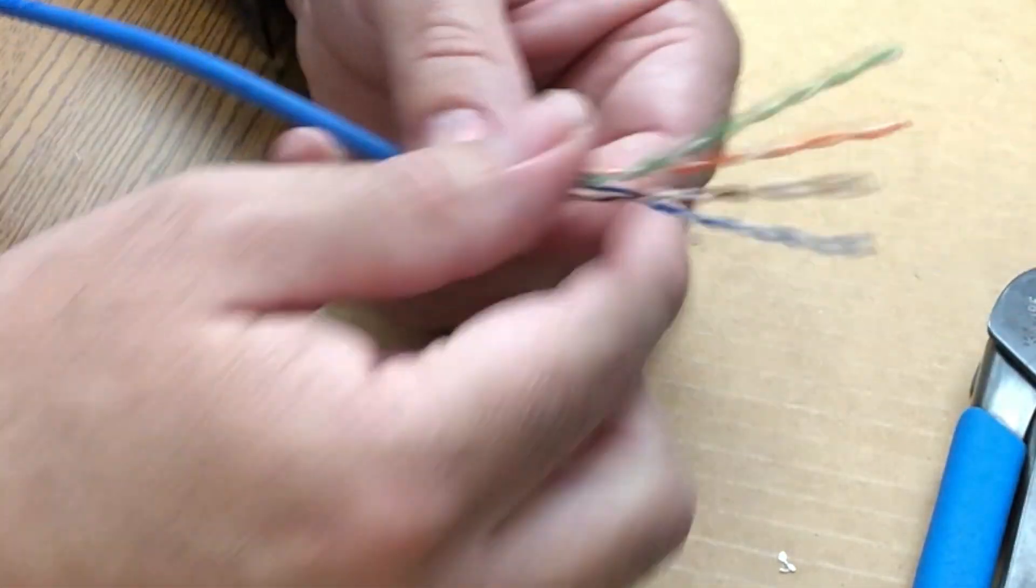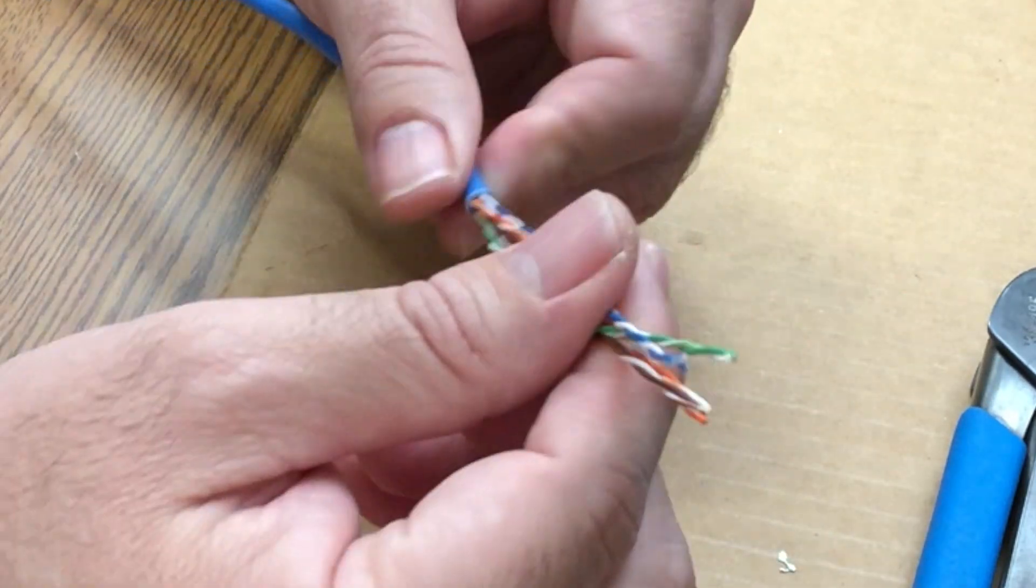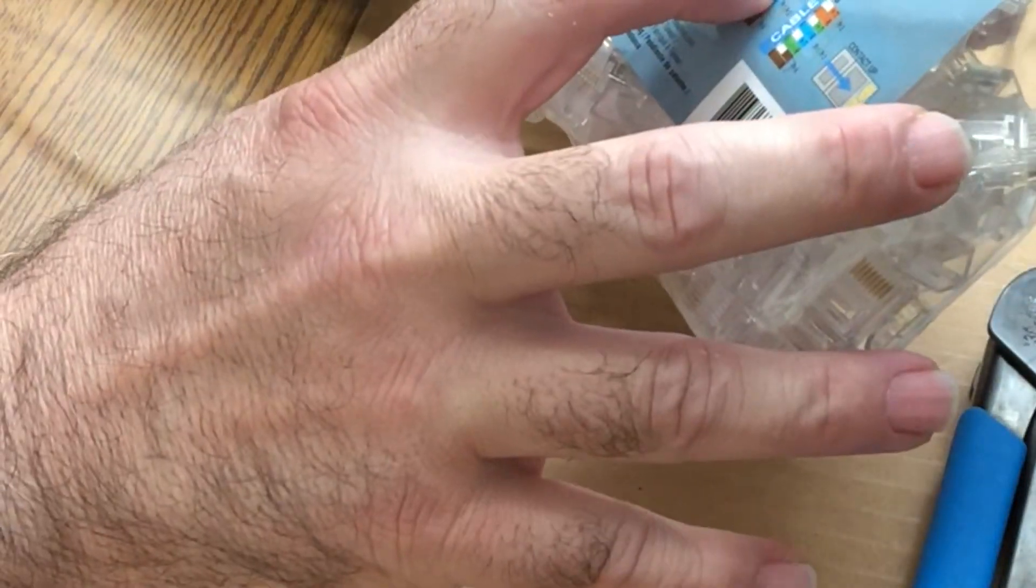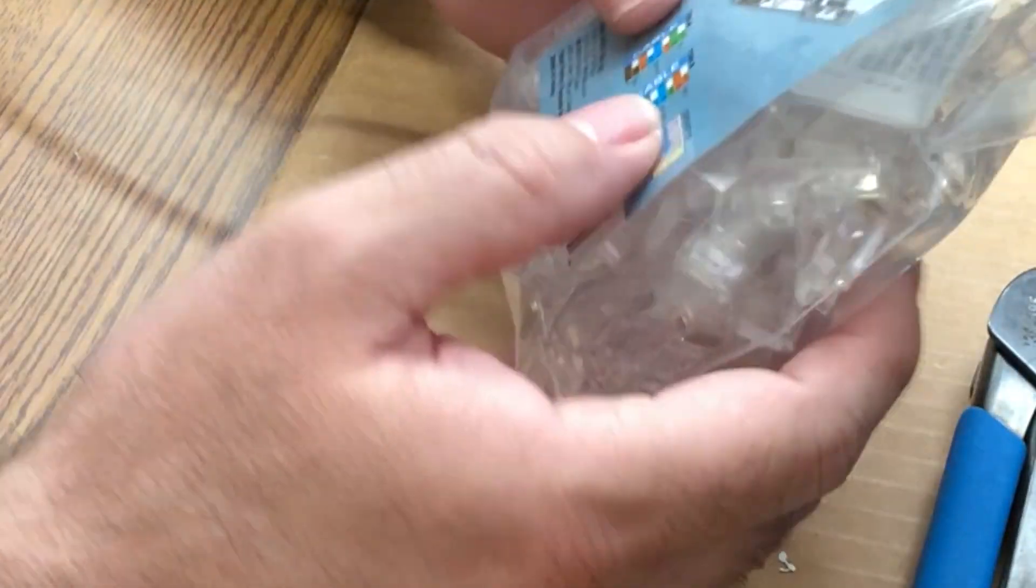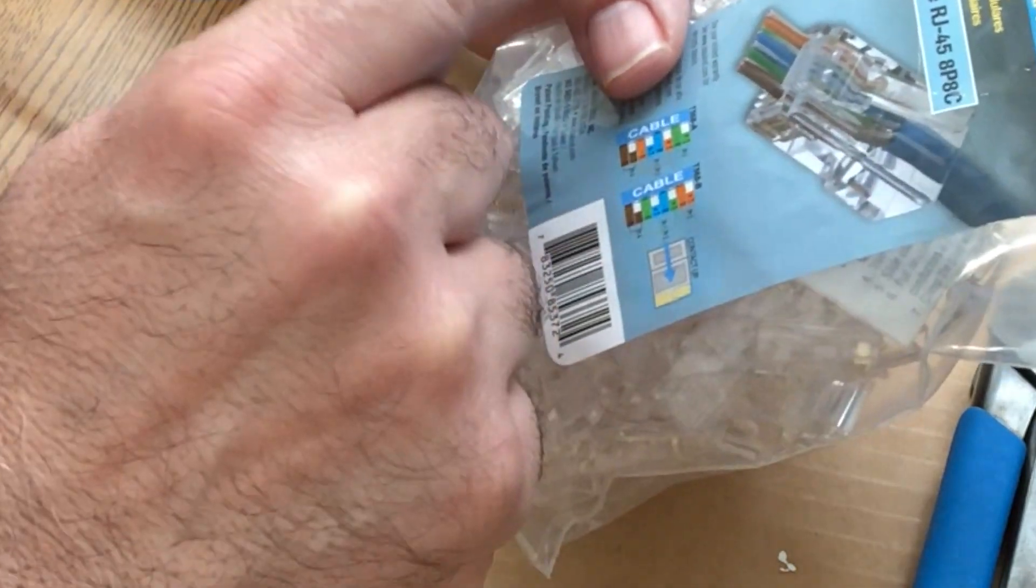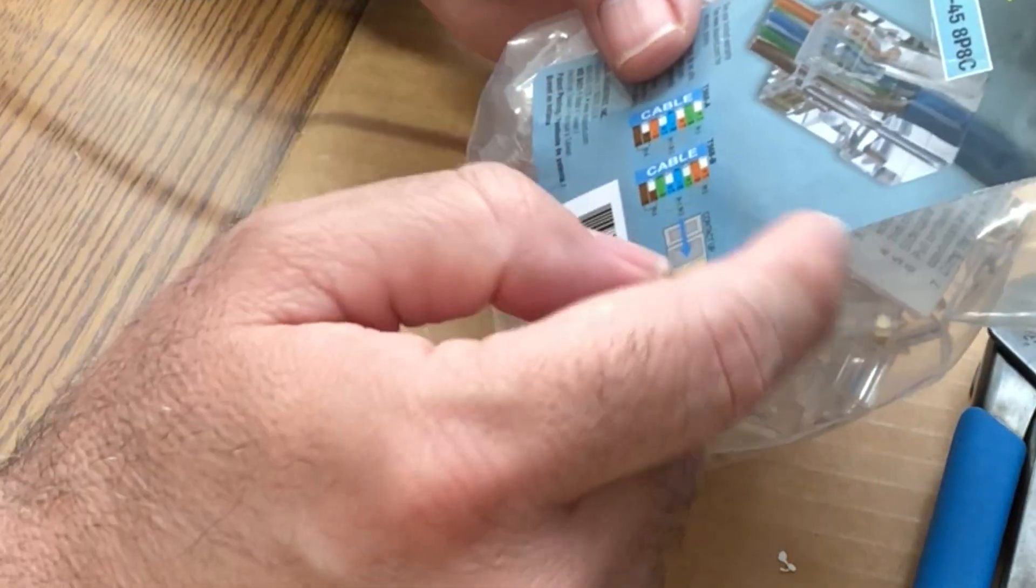There's two different standards when it comes to terminating category cabling. You got what's called 568A and the 568B standard. You want to make sure that when you terminate the cable like this that both ends are either A or both ends are either B.